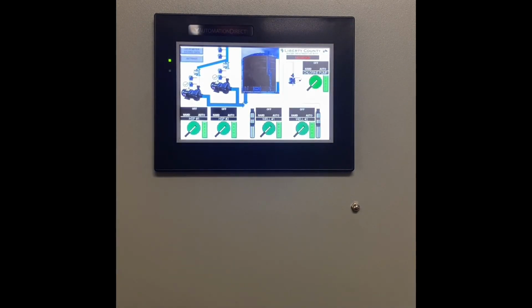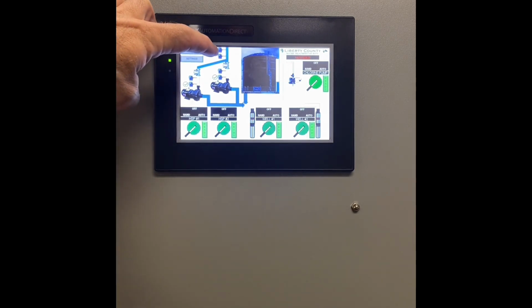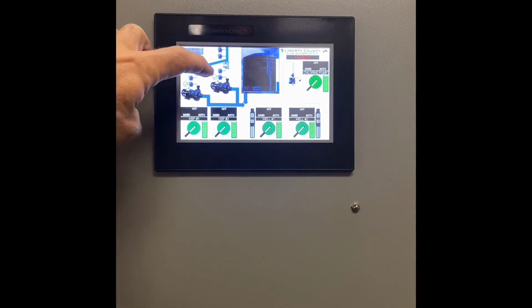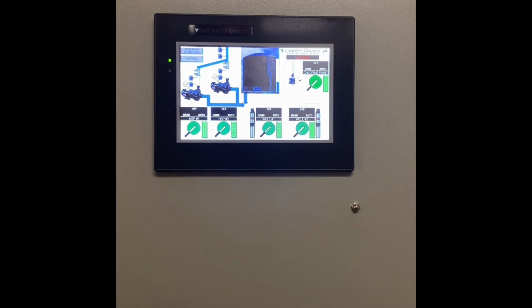Okay, now we're back on the main screen, and you'll notice that I have some images of pressure switches. 2 here, and then I have 2 more here and 2 more here. This system has a total of 6 pressure switches. The very top 2 pressure switches are the lead and lag pressure switches that control drinking water pressure to the people of Liberty County. The next 4 pressure switches are flow failure pressure switches.